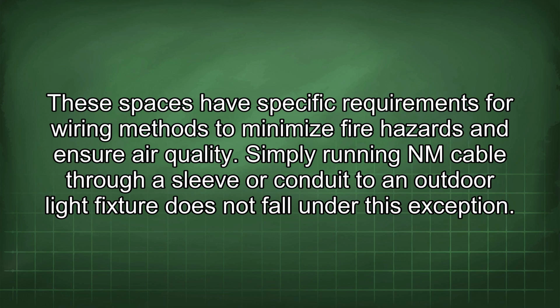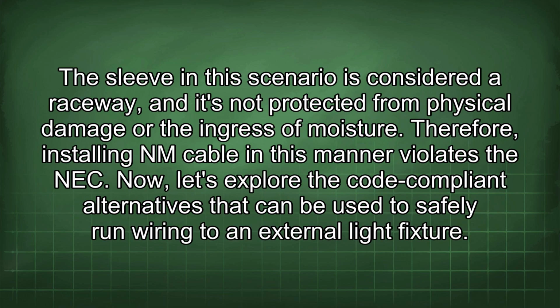Simply running NM cable through a sleeve or conduit to an outdoor light fixture does not fall under this exception. The sleeve in this scenario is considered a raceway and is not protected from physical damage or the ingress of moisture. Therefore, installing NM cable in this manner violates the NEC. Now, let's explore the code-compliant alternatives that can be used to safely run wiring to an external light fixture.